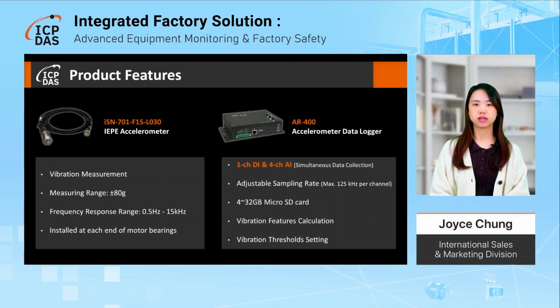The AR400 accelerometer data logger offers one digital input channel and 4 analog input channels, capable of simultaneously collecting data from up to 4 IEPE accelerometers. Each analog input channel supports a maximum sampling rate of 125 kHz. All captured signals are stored on its built-in 4 to 32 GB microSD card for offline vibration analysis. In this case, the AR400 accelerometer data logger calculates vibration features such as peak-to-peak acceleration and RMS velocity, and sets vibration thresholds based on the signals collected by the IEP accelerometer.